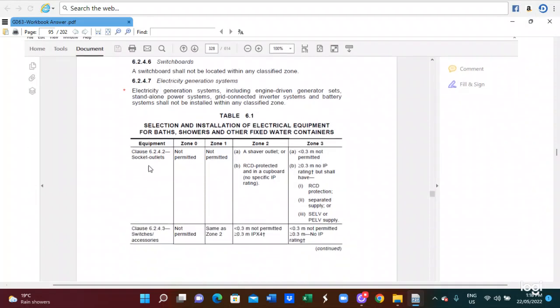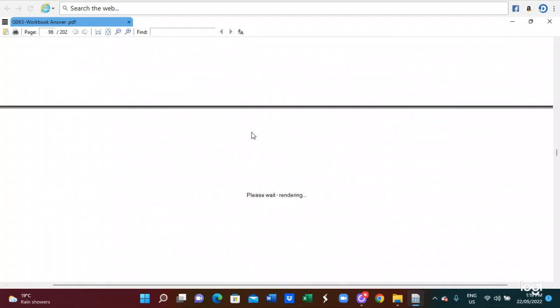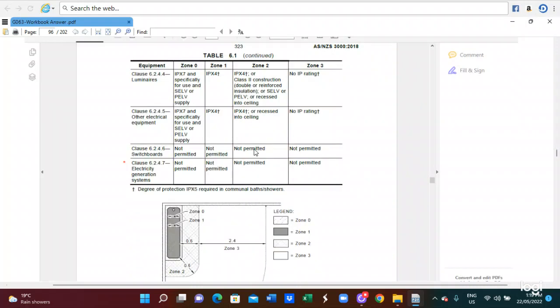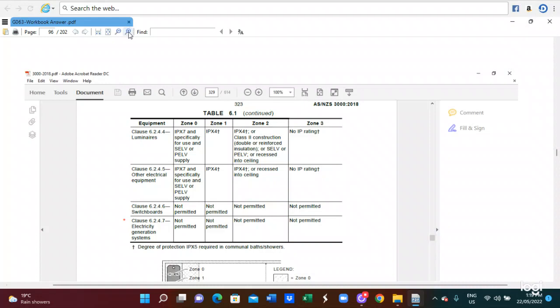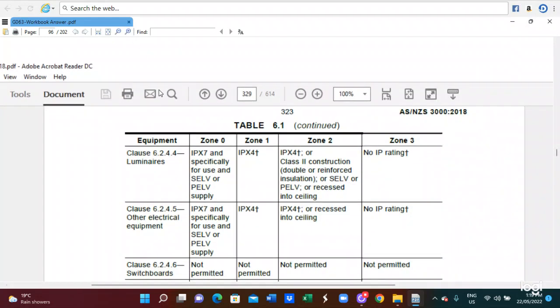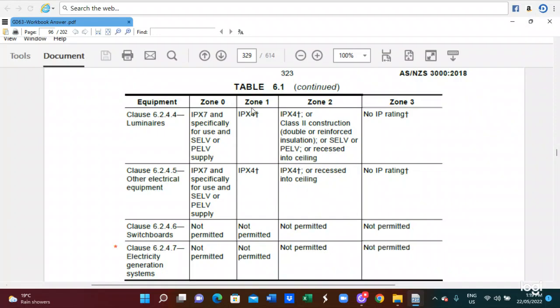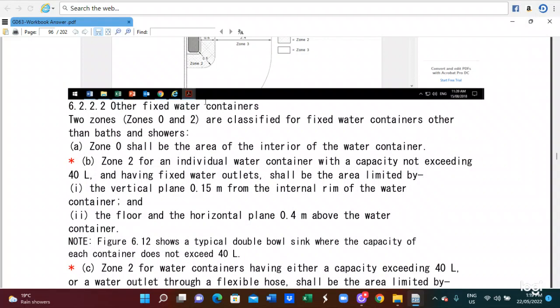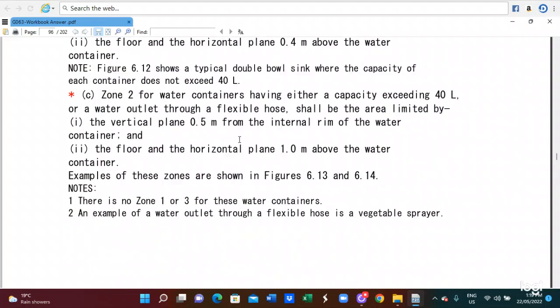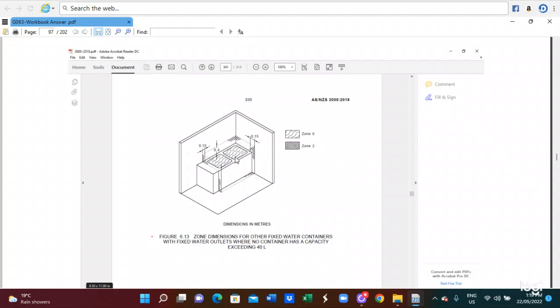Socket outlet connection, you have to follow Table 6.1. Table 6.1 is the selection and installation of electrical equipment for the bath, shower, and other fixed water container. So Table 6.1 gives the appropriate equipment IP protection we have to utilize. For fixed water containers, you have to follow clause 6.2.2.2. This is the fixed water container system you have to read through. And also this fixed water container and its diagram, why is a zone location. You can read in this diagram.